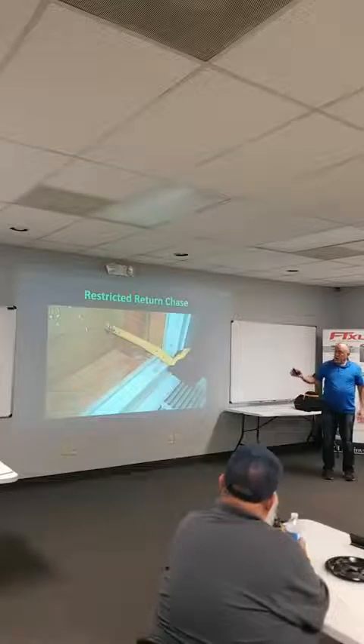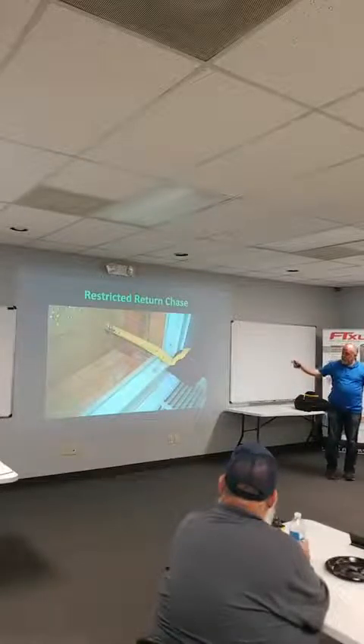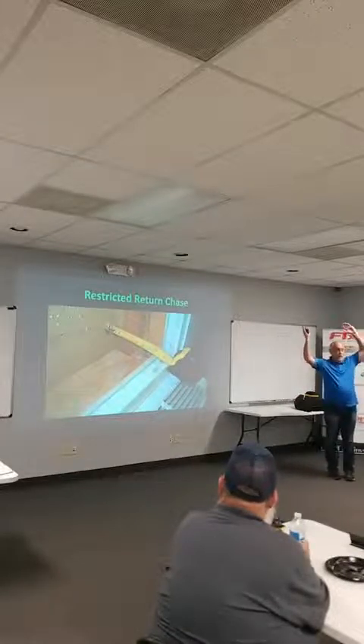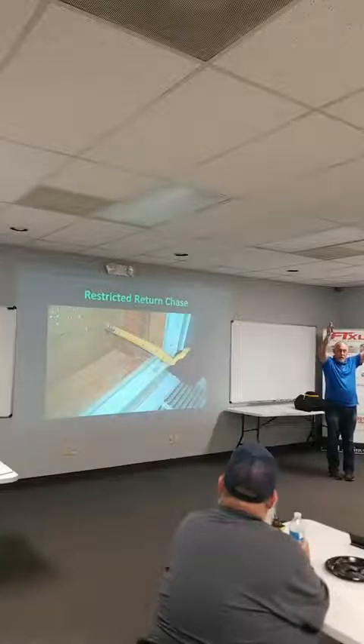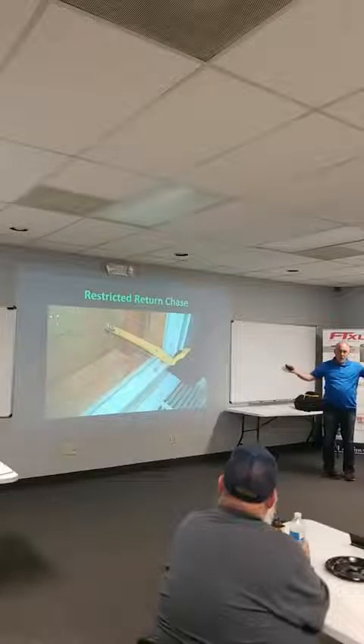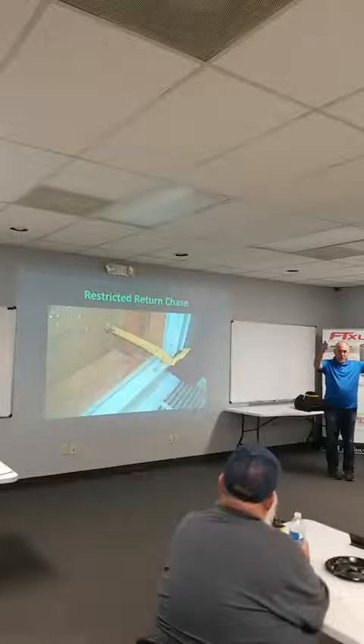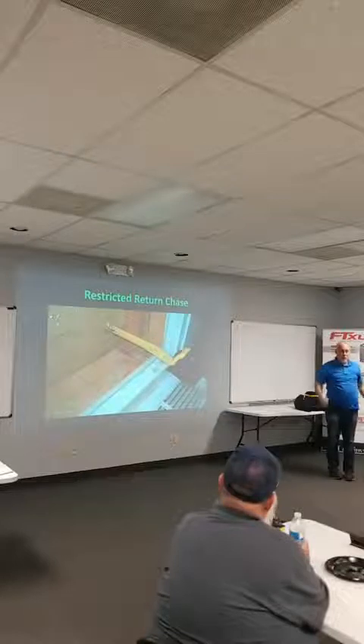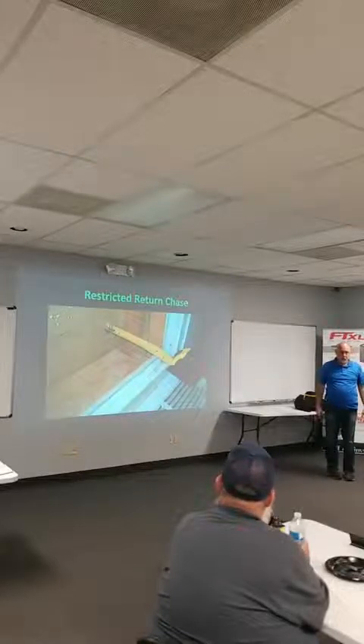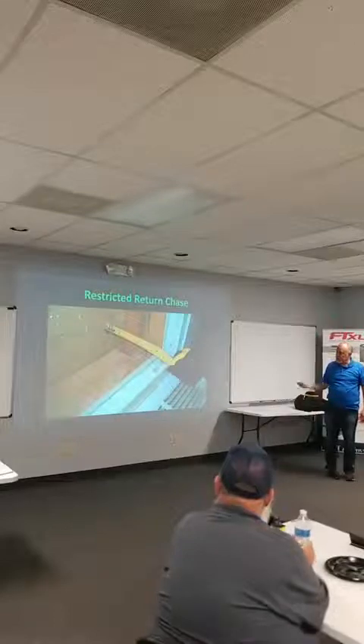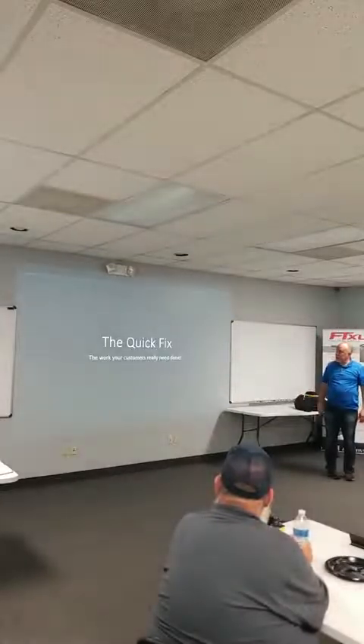You lost your velocity? No, it wasn't that. It was that he had this pan that went to a double 2x10, and then it went down a wall chase with a 2x4 wall. So literally it went from a 20 by 20 duct into two 2x10 joist pans, up into a 2x4 wall space and a filter grill, right? This is the kind of stuff, if you don't look at the system, if you don't chase it from one end to the other, you're gonna miss it. If we're not measuring the vitals, like static pressure, we're gonna miss it. And that's a big problem.